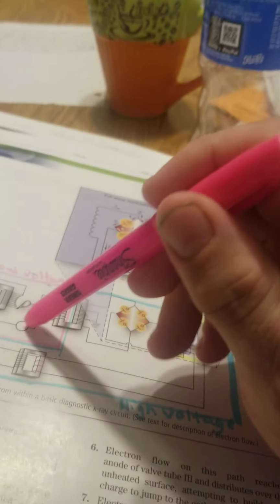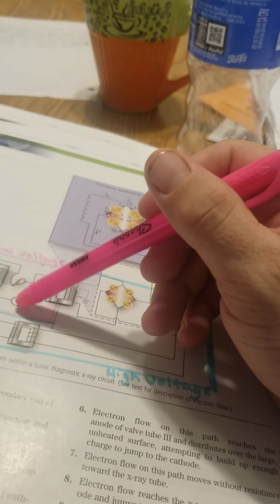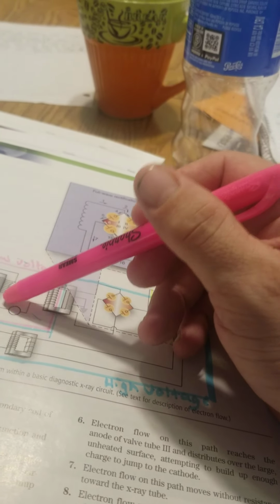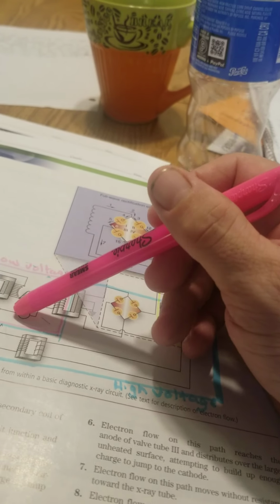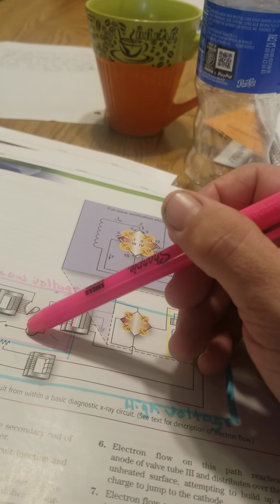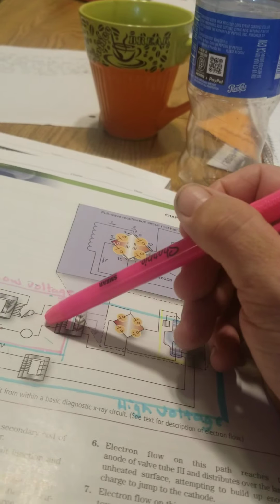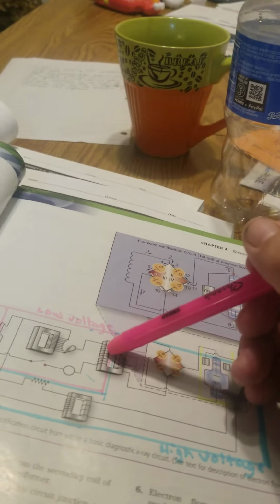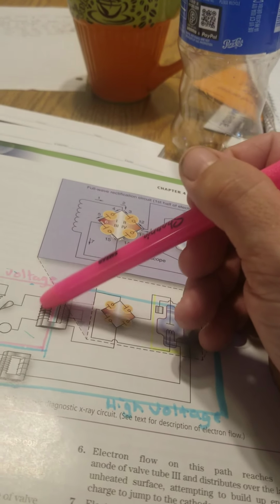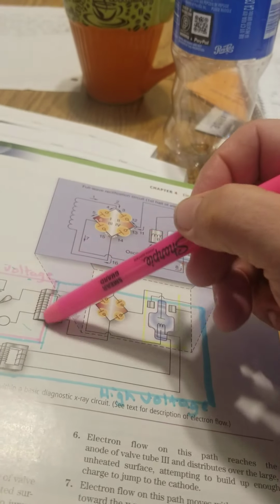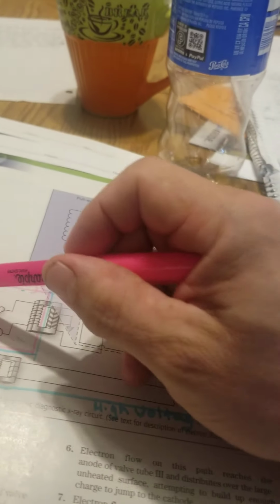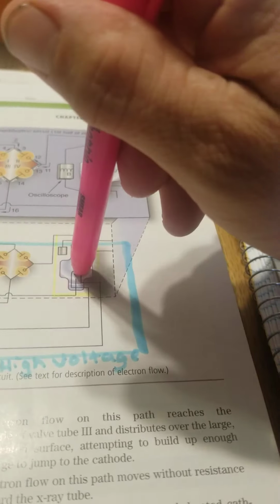And we have the operator's console where we are able to choose how much we want to use for our kilovolts, our kVp. We select that right here, and then it goes to a transformer. And this transformer, as you can see, is on the low voltage side right here. This is all basic low voltage, and then you got your high voltage over here, and then you got your filament voltage here. So there's three different kinds of current going through the X-ray device itself. But back to low voltage.